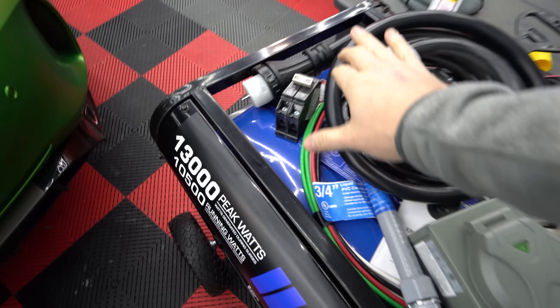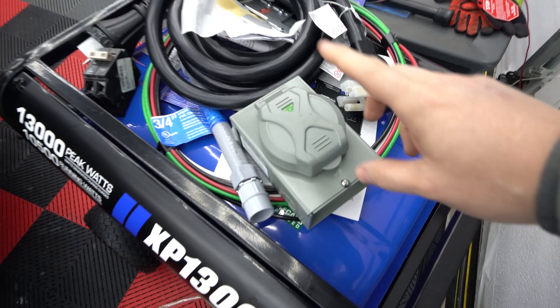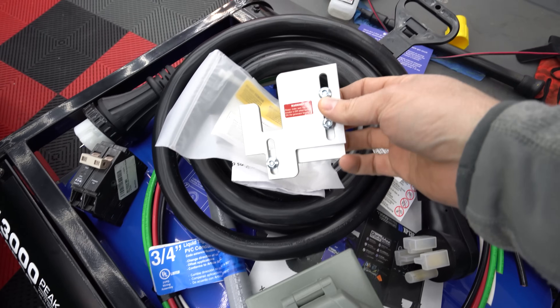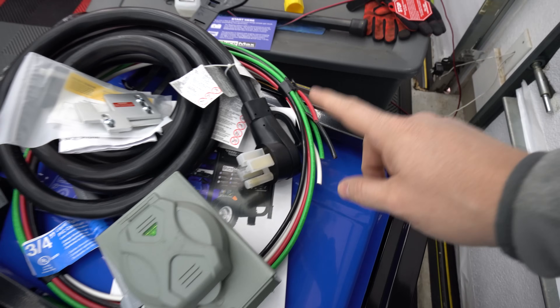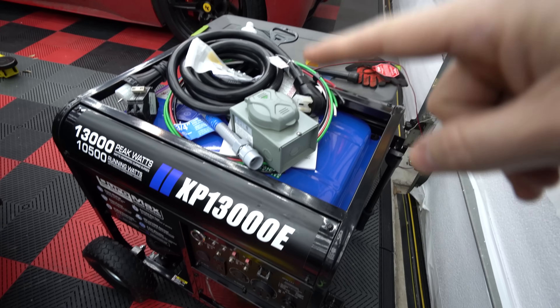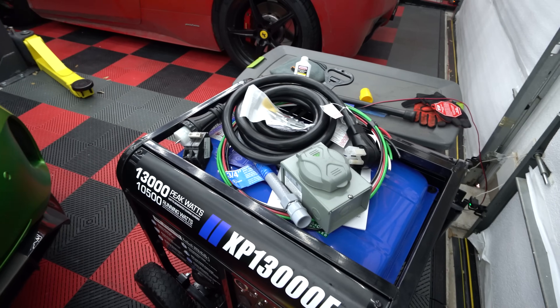It's been a few days and I have all the parts — it is now Wednesday, and tomorrow is when it's supposed to get cold, so we've got to get this installed today. Here's what we got: a 50-amp breaker that fits my box, a connection box, the power cord, a generator interlock kit — a really important piece — and some six-gauge wire, because it's going to be pulling 50 amps at 240 volts.